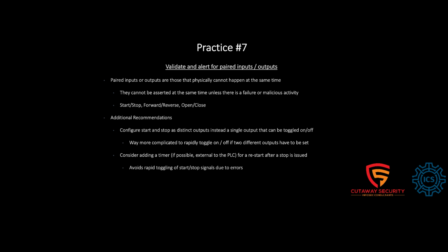Because that's how we define the paired inputs or paired outputs, meaning these two cannot physically happen at the same time. If, for example, a valve gives you feedback, both limit switches are on, meaning it's open and closed, well, then you know for a fact that something is wrong. It could be that the limit switches failed, or someone is manipulating values and they just try to enter a Modbus register full of ones, so all of them are now one, for example.